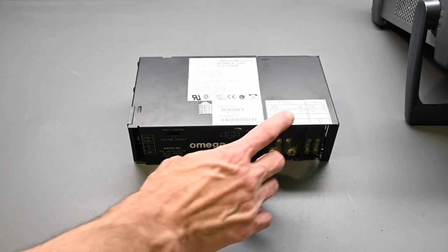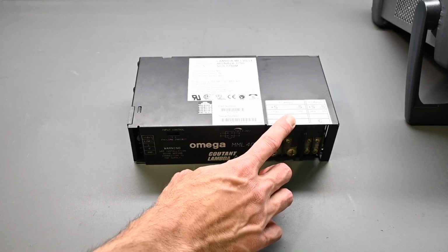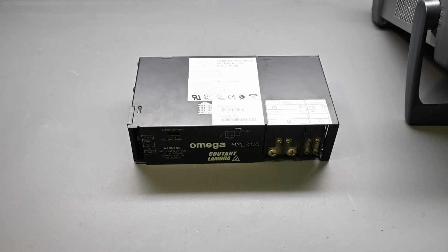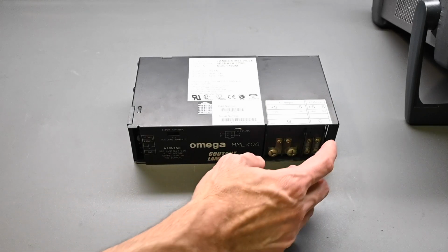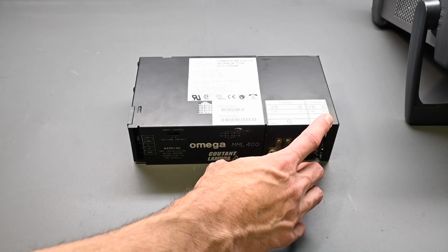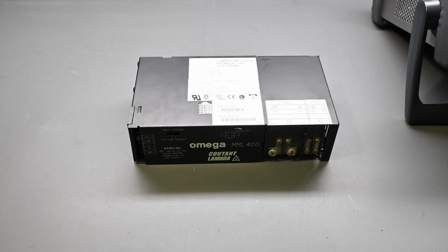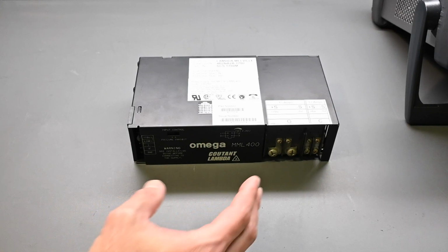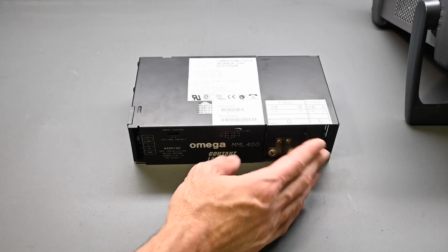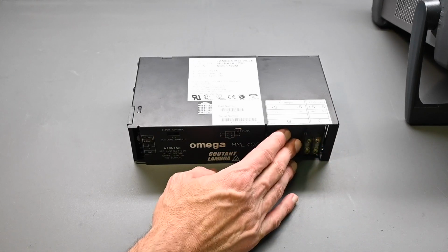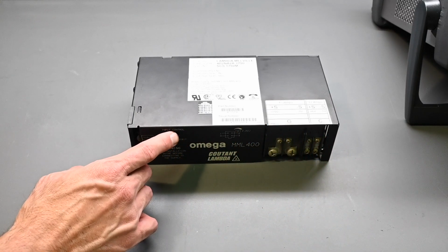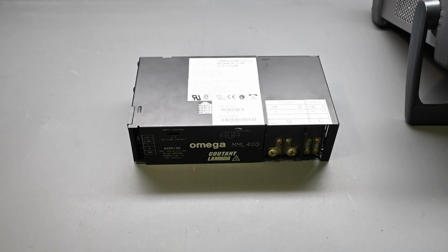So for example, if this was set to 24 volts and you were drawing 15 amps, that's 360 watts, so it would only leave 40 watts available power on the type C output. So as long as you don't exceed the 400 watts, then there's no problem whatsoever. Now, this has remote voltage sensing on both outputs. Other modules had some additional features. This has an unused area over here that some additional features could be installed. So the power supply was very modular and could be custom configured when it was ordered from the manufacturer.